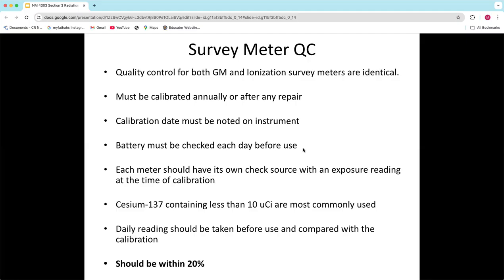And then each meter should have its own check source with an exposure reading at the time of calibration. So when they did the calibration, they put the date on there, and then they'll put the type of source that you have. And usually your source is a little disc or kind of a puck shape. Typically, it will be hooked to the side of your meter. It'll be connected, and they're a really low radiation source. It's really small, usually less than 10 mics or somewhere around there.